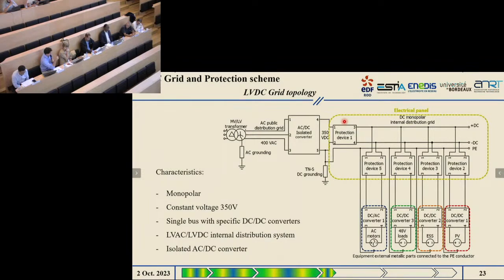Yeah, so I understand the point, but on this graph you are missing that on the AC side, between the transformer and the converter, you have another AC circuit breaker, which is conventional and works well. If the converter fails, it should be the AC circuit breaker that opens. So once again, do you really need this protection device?